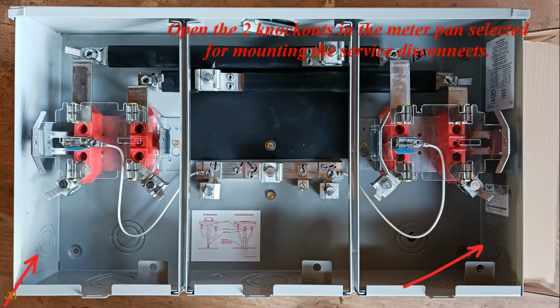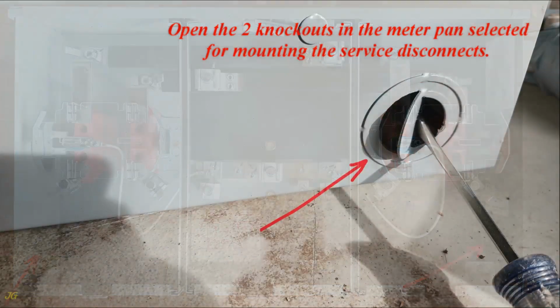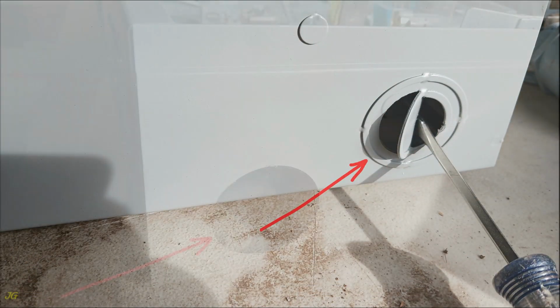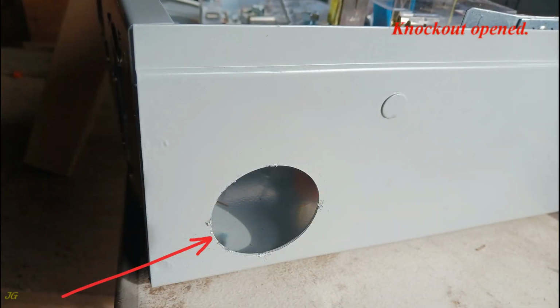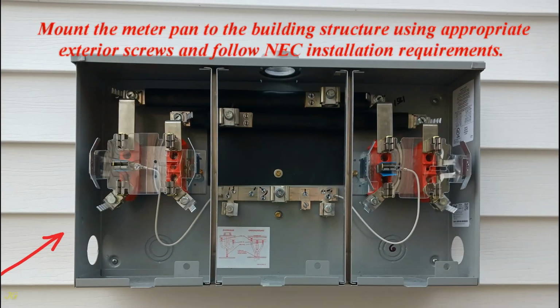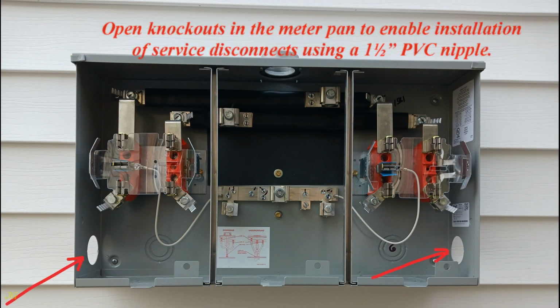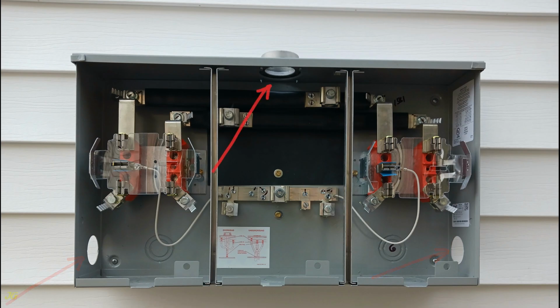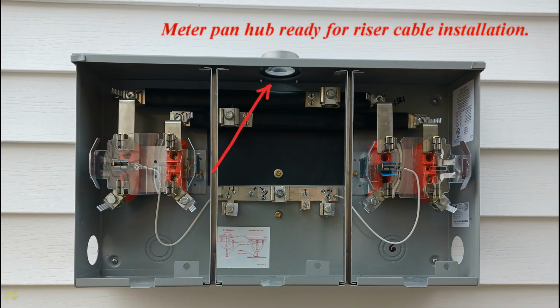Open the 2 knockouts in the meter pan selected for mounting the service disconnects. Knockout opened. Mount the meter pan to the building structure using appropriate exterior screws and follow NEC installation requirements. Open knockouts in the meter pan to enable installation of service disconnects using a 1.5-inch PVC nipple. Meter pan hub ready for riser cable installation.